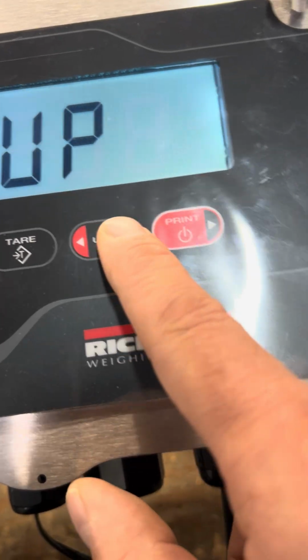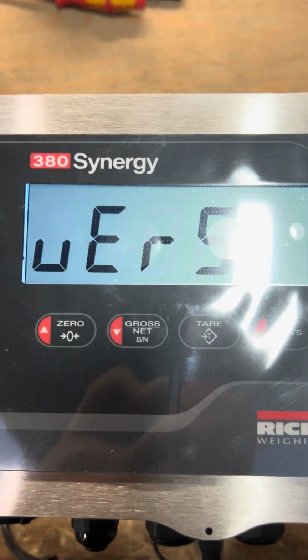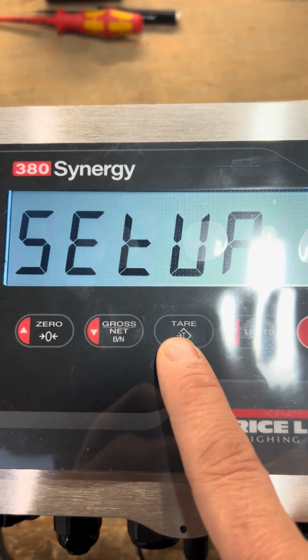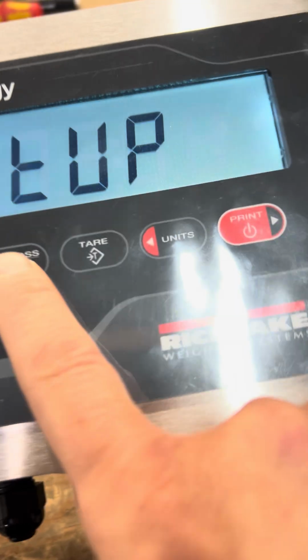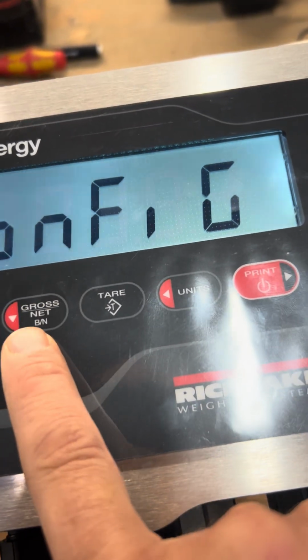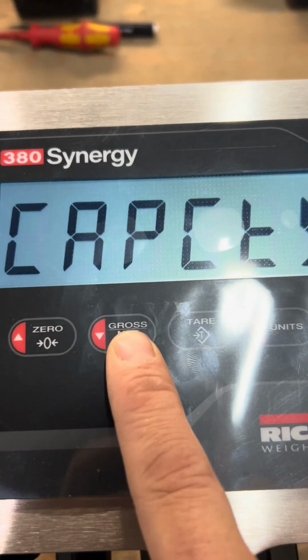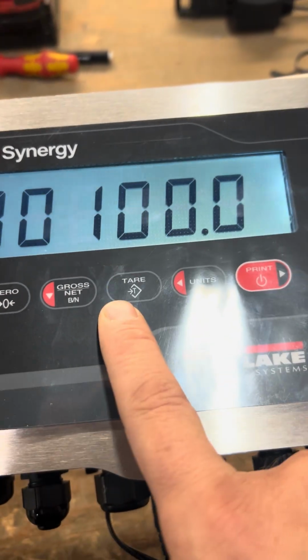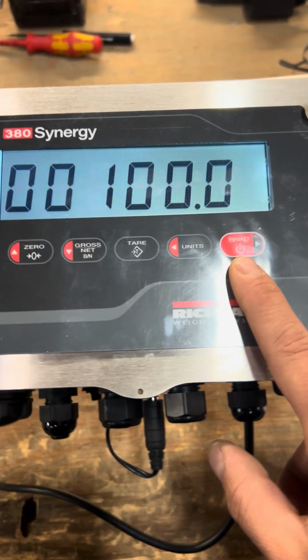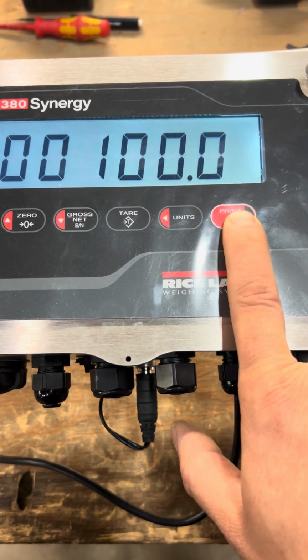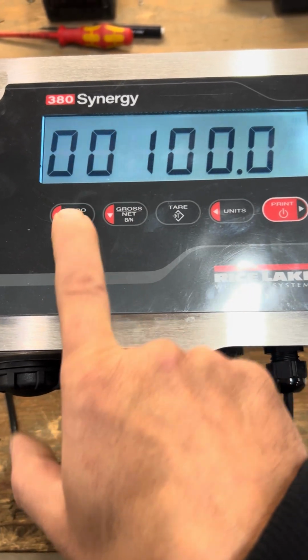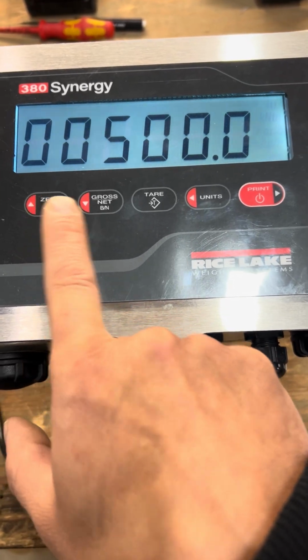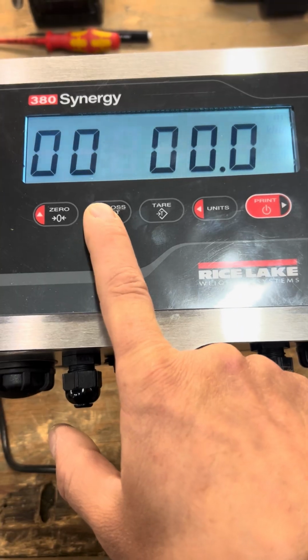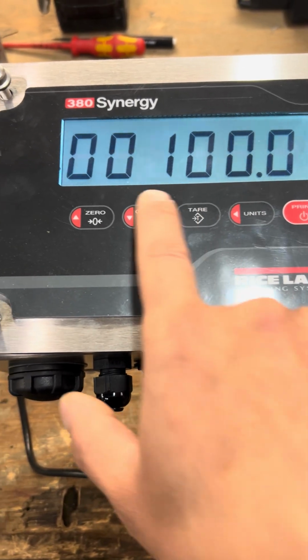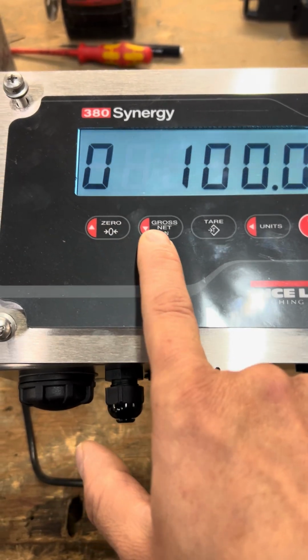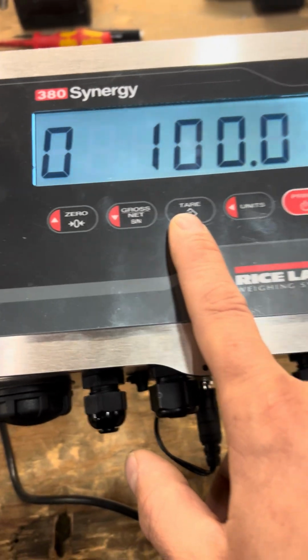Here you have errors. To move to the next, and Tare to confirm. So we need to go to the setup mode, go to configuration, capacity, we press again, go in. The capacity is 100 kgs. We can change this capacity by pressing this arrow, and we can change it to 2, 3, 4, 5, whatever we need. And we can make it 1000 by pressing the units button and moving here. So we will need 100 kgs, it will be okay.